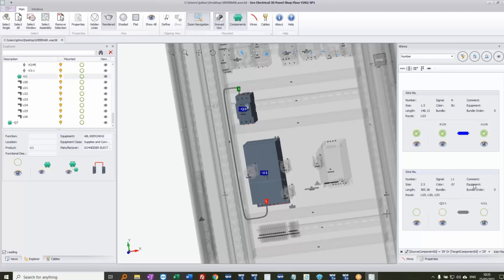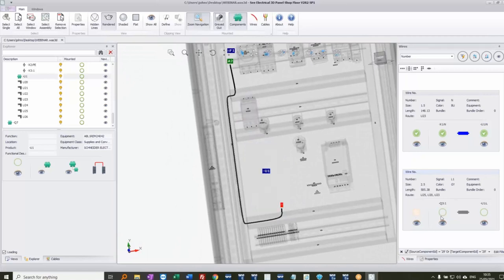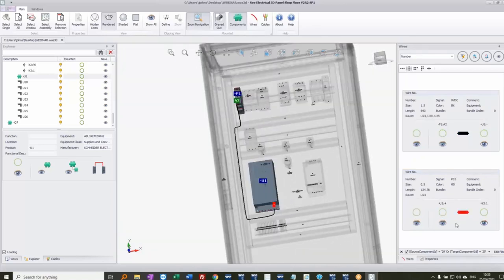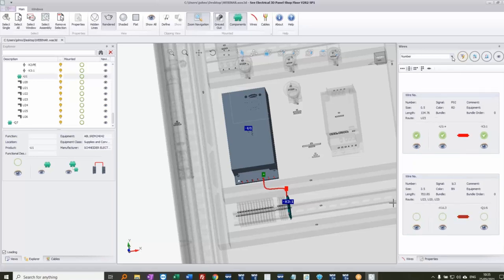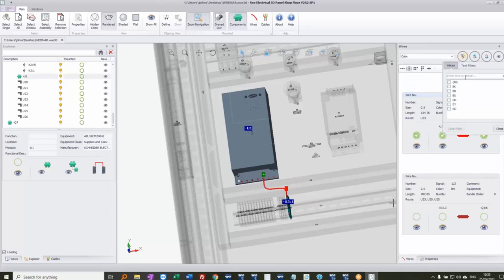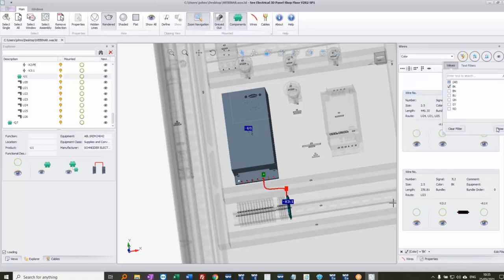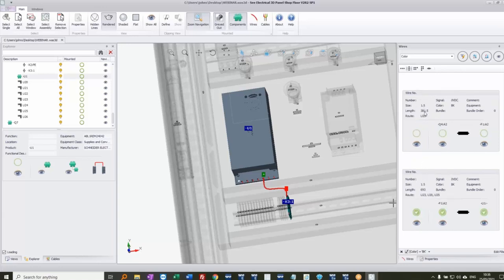I click 'Mounted' to confirm that wire is done, and the software automatically moves to the next wire. I can see the live incoming connection to the breaker at connection point one — very easy to follow. At the end of the day I can leave this and come back knowing exactly what's been done and what hasn't. This allows interruption or sharing of a job, and verifies that the wiring method is consistent with the documentation.